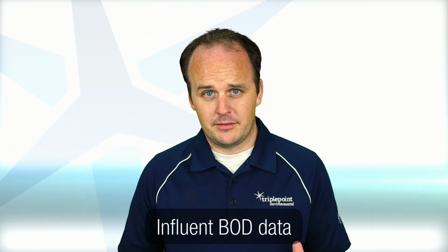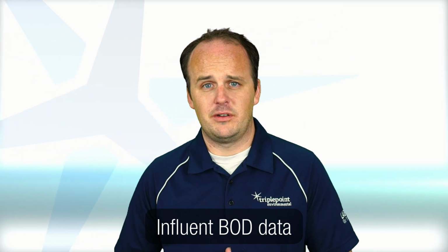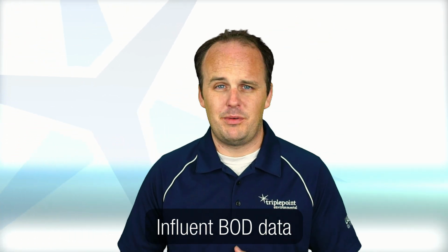Influent BOD data. This is another thing that we run into. There's a lot of lagoon systems that don't keep influent BOD data because they're not required to by the state. And so nobody knows what's going into their lagoon. And you can definitely make assumptions based on population equivalent. But if you've got an industry on your system and they're putting BOD into your system and you don't know what your influent BOD is, it could be much, much higher than you think it is.